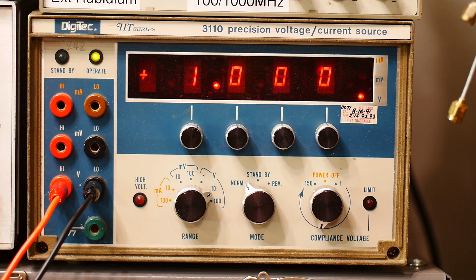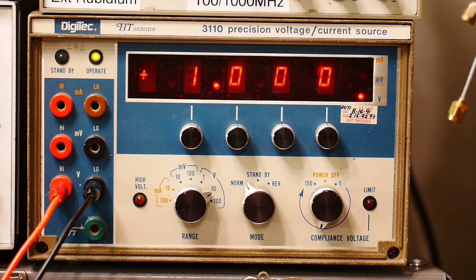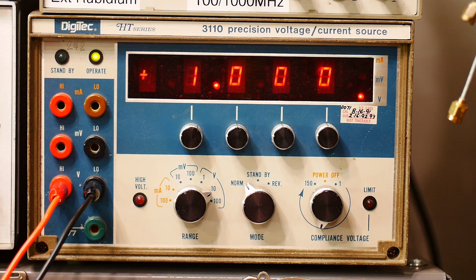And unfortunately, it's quite a bear to service. There's about 20 potentiometers on the back. So for every single range, I think there's a gain and an offset, and maybe, I don't know, it's tricky. I've tried to calibrate it in the dark. I've tried to calibrate it to other instruments that I trust, but it is a tricky thing to do. It'd be nice to have a manual for it. But anyway, it is useful. It's not too high precision. It's only 3.5 digits or something like that, maybe 4 digits.